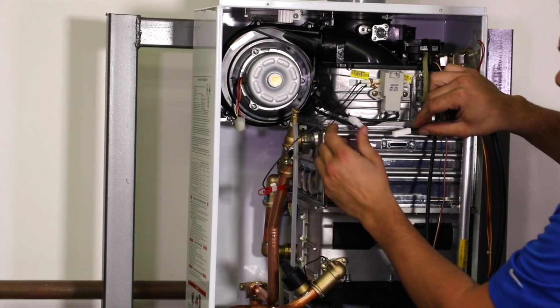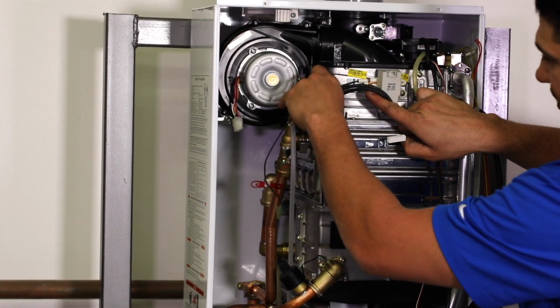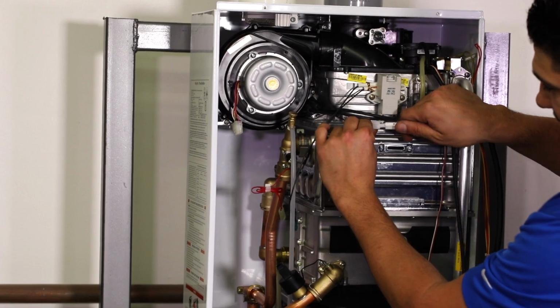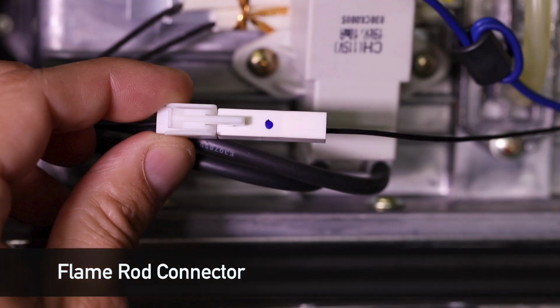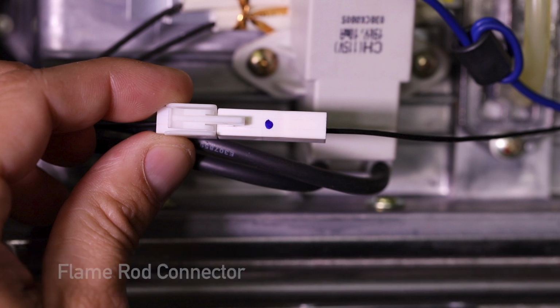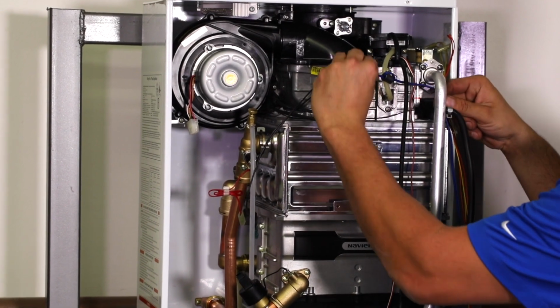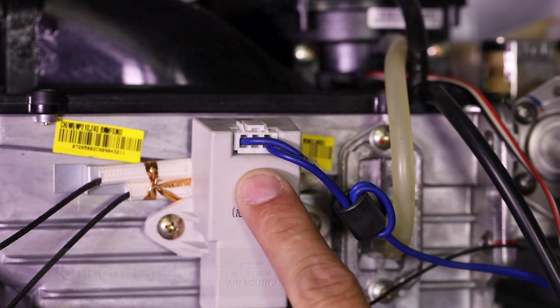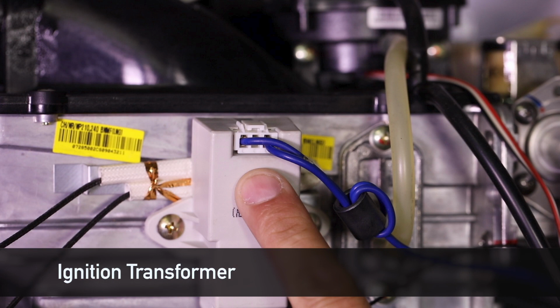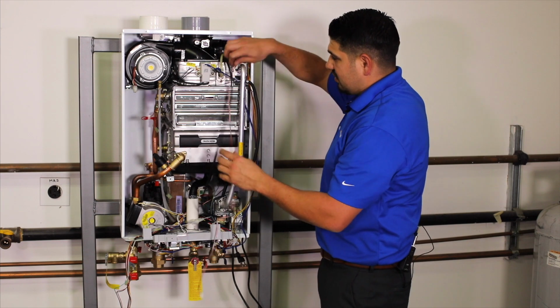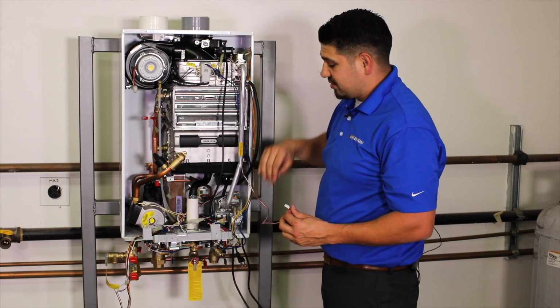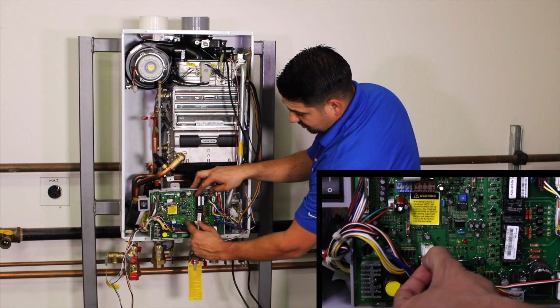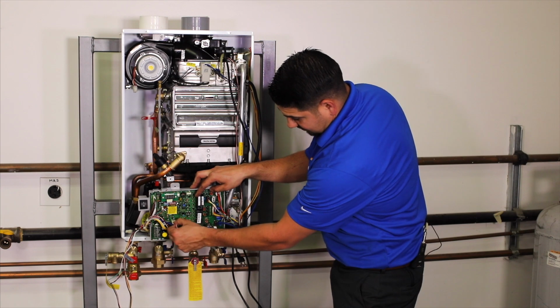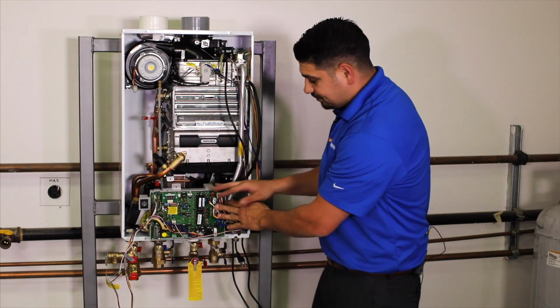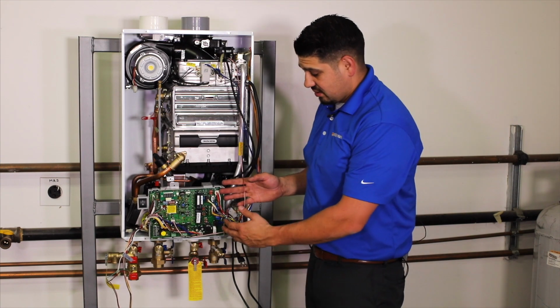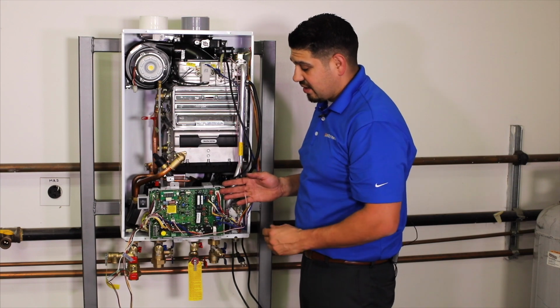We have your black wire here, and this goes to your flame rod, which is clear on the other side of your burner. So it's going to go right under. We have our ignition transformer, which is this large blue wire. Finally, as far as it goes on this side, we got our air pressure sensor. That's going to plug in right to the front of the board, right where this yellow sticker is, right below that. And one of the things about our computer boards is every connection on our computer board is unique. So you can't crisscross, mismatch, or plug it into the wrong area. If it doesn't fit, it doesn't go there.